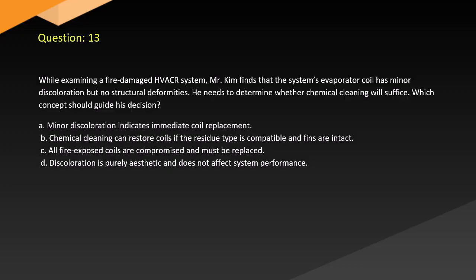Question 13. While examining a fire-damaged HVACR system, Mr. Kim finds that the system's evaporator coil has minor discoloration but no structural deformities. He needs to determine whether chemical cleaning will suffice. Which concept should guide his decision? A. Minor discoloration indicates immediate coil replacement. B. Chemical cleaning can restore coils if the residue type is compatible and fins are intact. C. All fire-exposed coils are compromised and must be replaced. D. Discoloration is purely aesthetic and does not affect system performance.